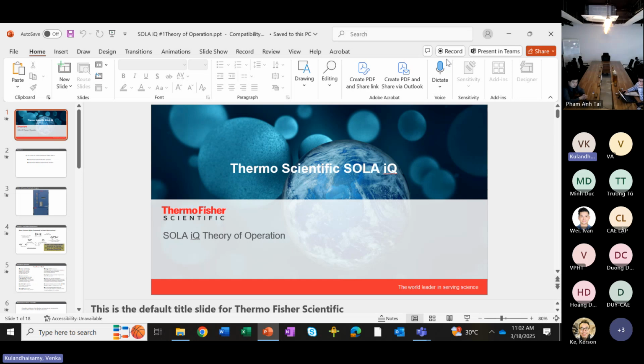For SOLA IQ, we have different software. That software we will provide free to the customer. Whenever they purchase the SOLA IQ, the software is in the package. The software is called Auto Config. The Auto Config software can control the SOLA IQ analyzer from your computer system. Meaning the customer needs to load the Auto Config software onto the computer, and then the computer is connected to the SOLA IQ. Then they can operate the SOLA IQ from the computer, that means from the DCS or whatever, they can operate.